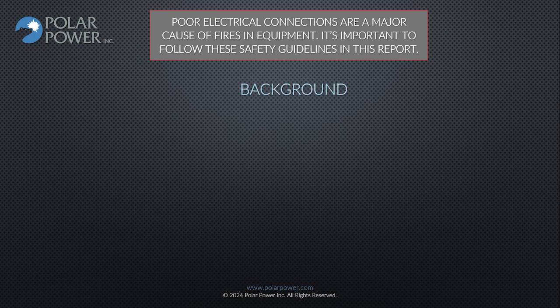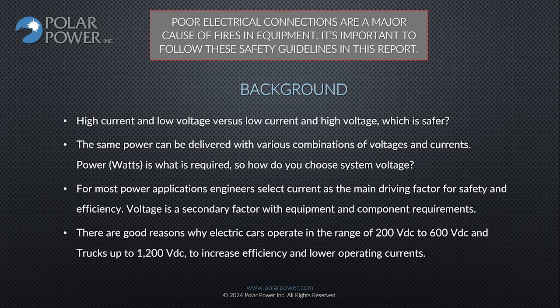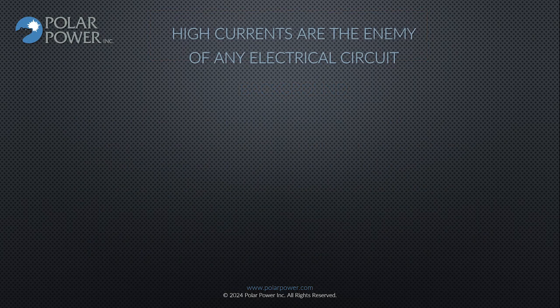Background: high current and low voltage versus low current and high voltage, which is safer? The same power can be delivered with various combinations of voltages and currents. Power, or watts, is what is required. So how do you choose system voltage? For most power applications, engineers select current as the main driving factor for safety and efficiency. Voltage is a secondary factor with equipment and component requirements. There are good reasons why electric cars operate in the range of 200 VDC to 600 VDC and trucks up to 1200 VDC, to increase efficiency and lower operating currents.